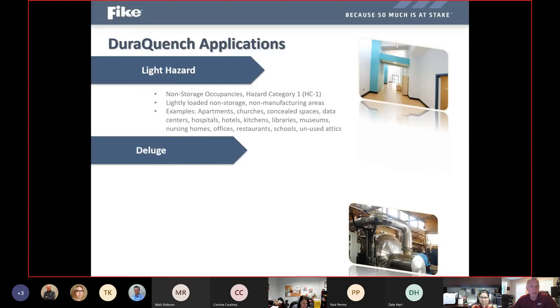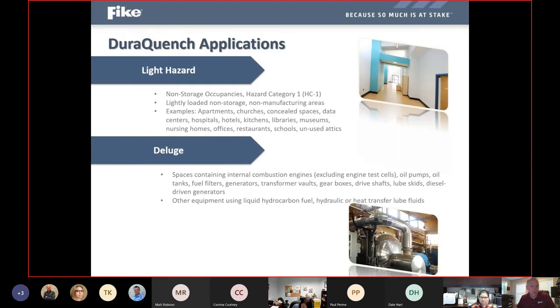Water mist is becoming much more popular with a wider range of uses, everything from light hazard systems. In our light hazard listing, it's very similar to a sprinkler system. It's a wet pipe system with every head being closed, and once that head melts off at 135 degrees, it sprays out water. But instead of spraying out large amounts of large-droplet sprinkler water, it comes out as a mist, so it leaves a lot less collateral damage behind.